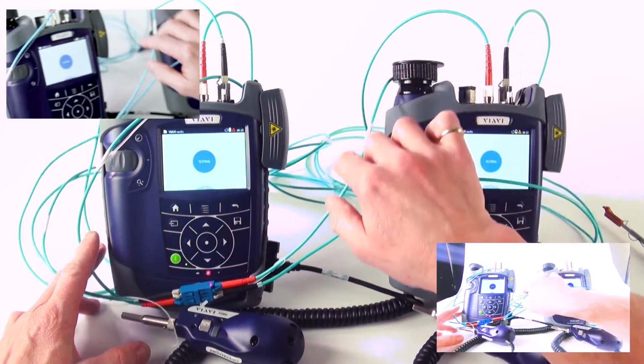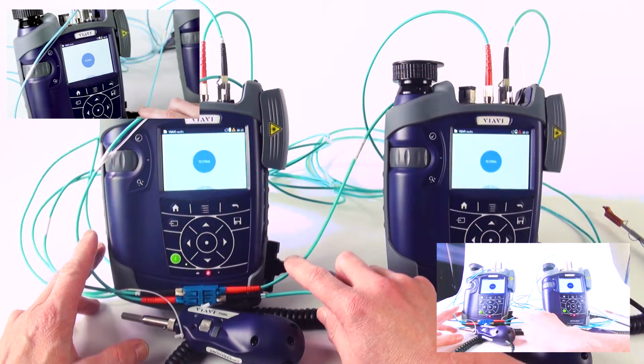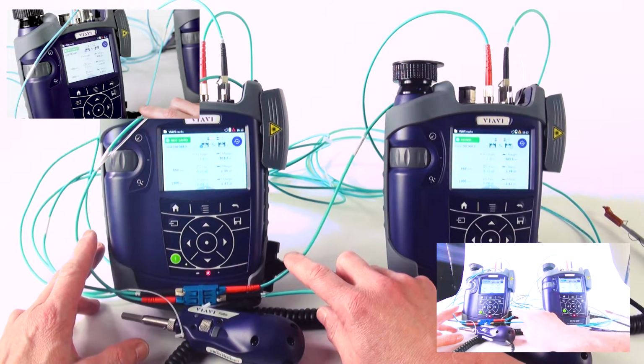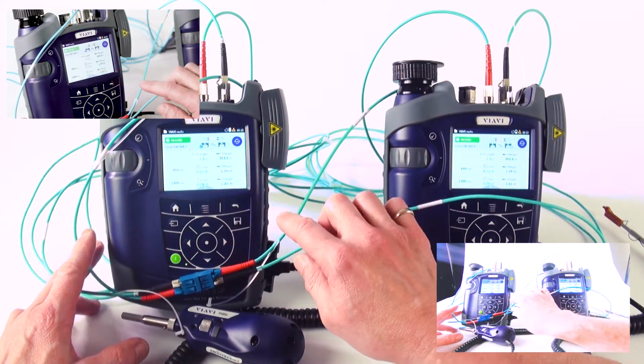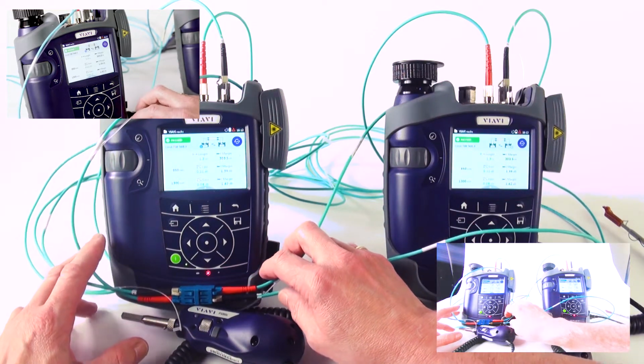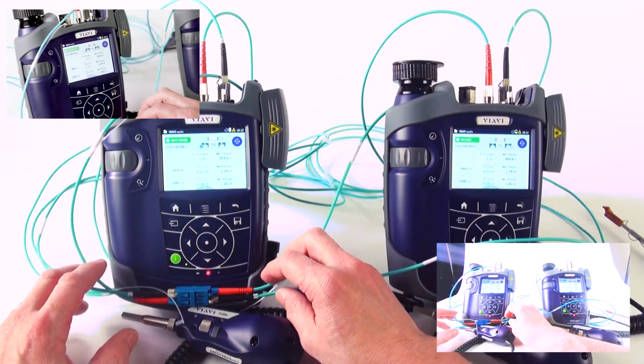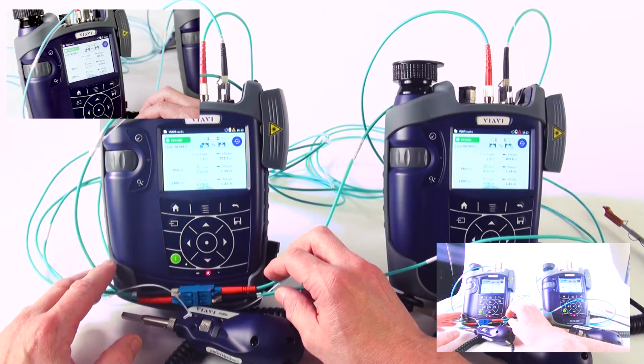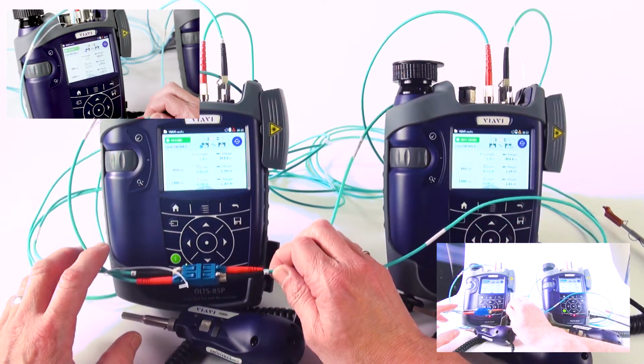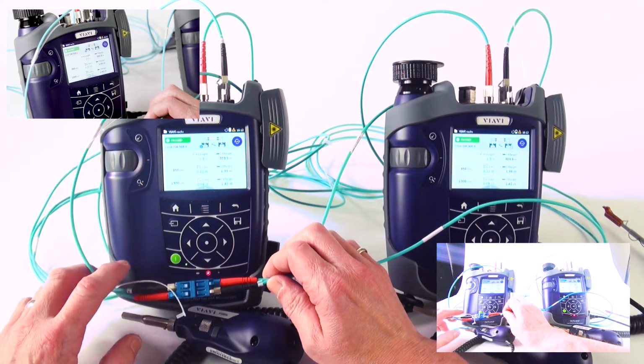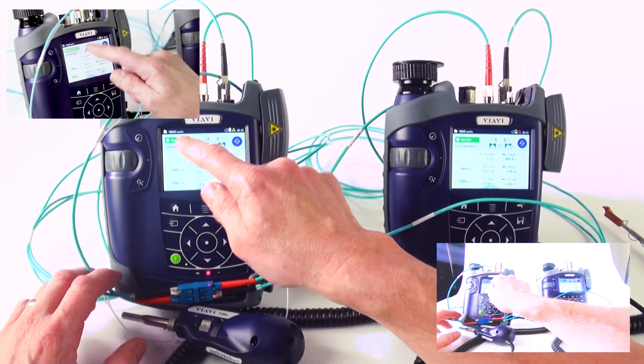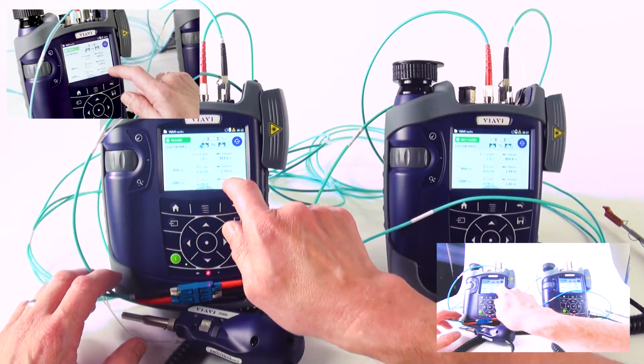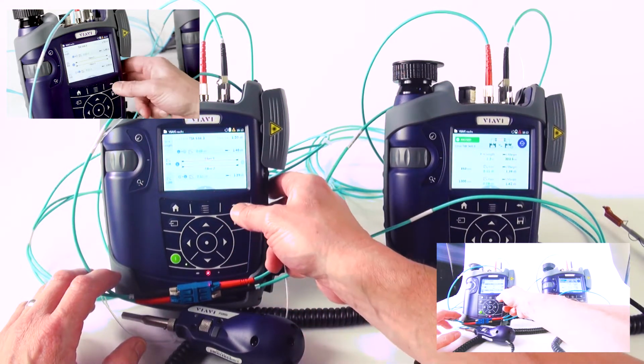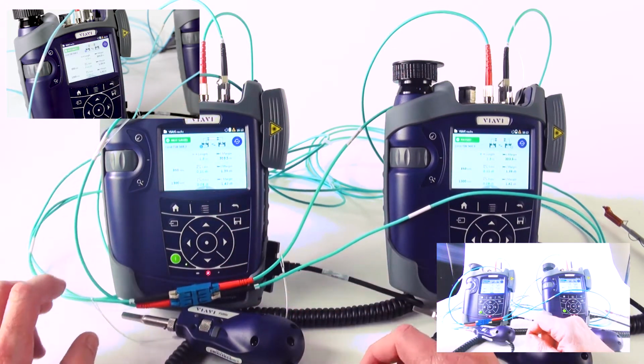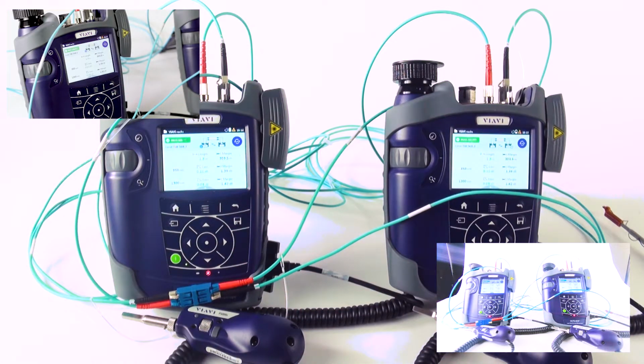I'm doing this from the local unit, but I could do it from the remote as well. It does an auto test and passes, but what I really want to look for is my loss values. For multi-mode, losses should be below a certain threshold - multi-mode and single mode are slightly different - but you want losses that are quite low to confirm your test cords are good and your reference was successfully set. This is my summary results screen, and I can drill into the details to see how much loss I have on each fiber.